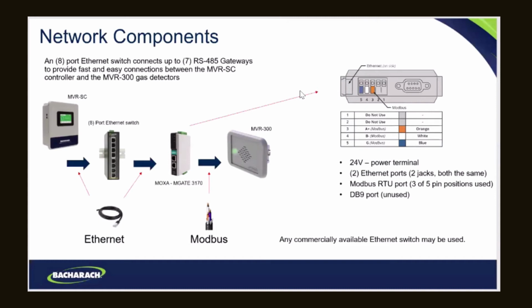Do they have to set the parts per million in the setup? Well, we have factory default alarm points, but you can modify those to whatever alarm point you want. The concentration 0 to 2500 is a feature of the sensor element itself. You can set those alarm points at something other than our factory defaults. And I don't know what those factory defaults are off the top of my head right now. I got Larry looking for factory defaults.